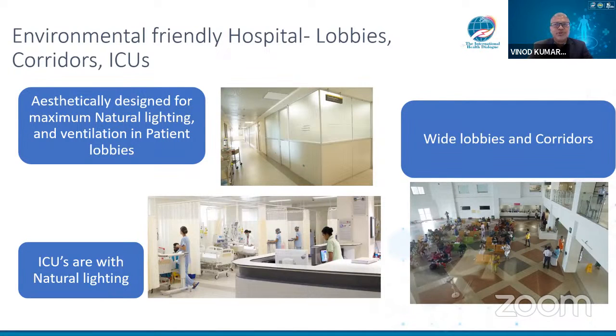And as you know, if you have an enclosed waiting area, air conditioning is generally provided, but we don't provide exhaust ventilation. The waiting areas are where almost all the sick people come and sit together before they get treated, so automatically the air becomes highly contaminated. It's a contaminated area basically. So ventilated waiting lobbies and corridors are generally better than providing only air conditioning, and then providing exhaust fans with at least a minimum of 10 to 12 air changes per hour brings high efficiency in the air quality in the waiting area. So environmentally friendly hospitals, lobbies and corridors are a part of this system.